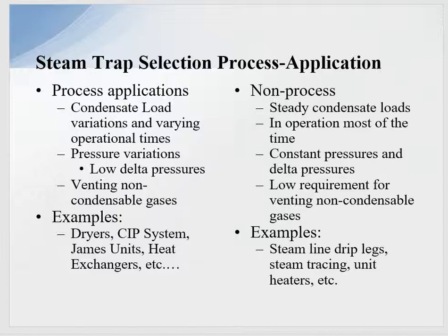Typically loads are always steady — might be 250 pounds per hour, might vary 75 to 100 pounds per hour, but not much variation. In operation most of the time, a lot of these units will stay in operation 365 days a year. This gives us a constant pressure and delta pressure, making it easier to select and size the steam trap. Low requirement for venting non-condensable gases because it's always in operation. Examples: steam line drip legs, steam tracing, unit heaters.